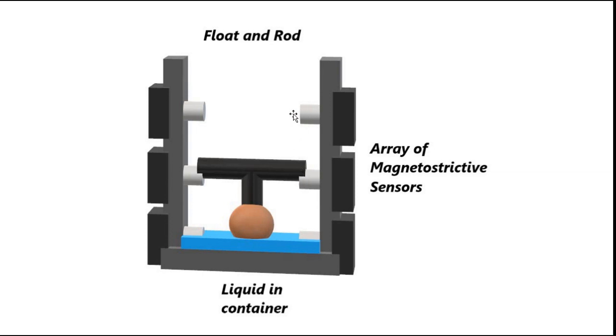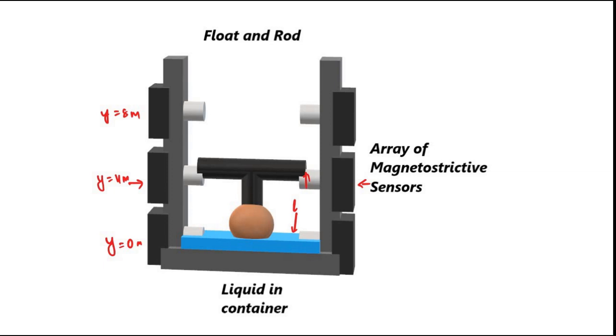For continuous measurements, the sensors are placed at fixed separation gaps — for example, at y = 0 m, y = 4 m, y = 8 m, and so on. Whenever a particular sensor is triggered, it gives us information about the liquid level at that position. Mathematical calculations account for the length of the float from that point to the liquid surface, which is subtracted to give the actual liquid level.